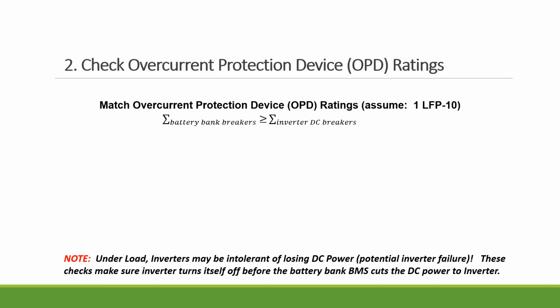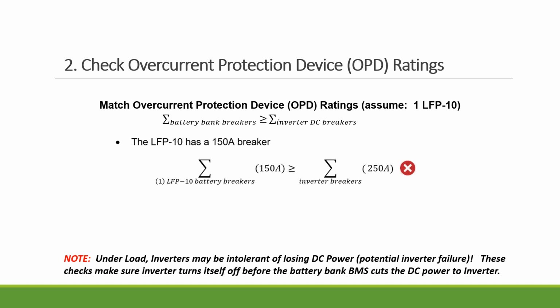power comes through. If the battery bank breaker size is smaller, then the battery bank is going to shut off first, right? The DC breaker is going to shut off. In that case, some inverters may not handle that very well, because they have control circuits based on the DC side. That's why for our Schneider equipment, we suggest that the battery bank breaker sizes, if you group them together, have to be bigger than the inverter DC breaker size.